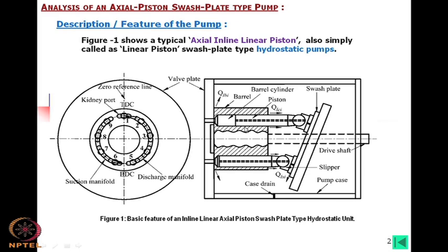Now, as the pressure changes during the rotation, the suction and compression, as well as in this valve, there is also a transition zone. Depending on that, torque on the input shaft as well as the swash plate shaft vary. So, while we are changing the angle, particularly in case of variable displacement, or when this is being used for a constant displacement or some constant pressure, constant torque, whatever may be the feature, in that case we need to control that swash plate torque. So, for that it is essential to know what is the torque acting on the swash plate at any instant.